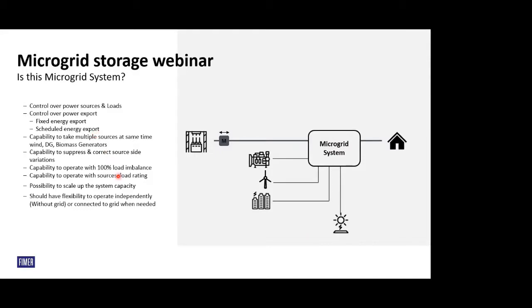We can also use other renewable sources like wind and biomass generators, rectify and filter out the harmonics, correct its voltage and frequency variations, and send it back to the grid if the loads are lesser. It can successfully handle imbalances in the load without any problem, and you can scale it up at any point of time. For example, you build a whole microgrid system today without a grid, and if tomorrow a grid comes nearby, it will easily be able to take the grid and work along with it.